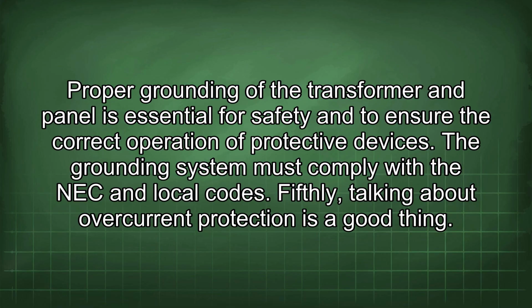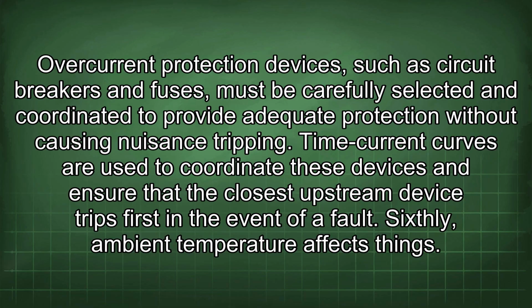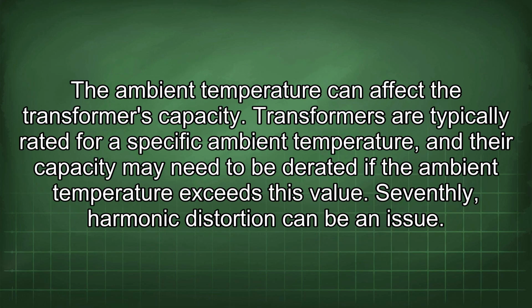Fifthly, overcurrent protection. Overcurrent protection devices, such as circuit breakers and fuses, must be carefully selected and coordinated to provide adequate protection without causing nuisance tripping. Time current curves are used to coordinate these devices and ensure that the closest upstream device trips first in the event of a fault. Sixthly, ambient temperature affects things. The ambient temperature can affect the transformer's capacity. Transformers are typically rated for a specific ambient temperature, and their capacity may need to be derated if the ambient temperature exceeds this value. Seventhly, harmonic distortion can be an issue.